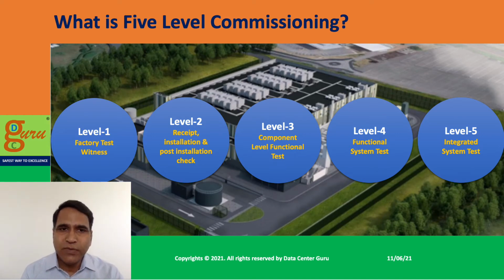Then level 2. Level 2 commissioning is all about whatever material is landing or being delivered on the site. Somebody has to check and ensure that all those systems, materials, and items delivered on the site are as per the design and specifications. Also, because normally when it gets delivered you cannot check the performance, but the specification and healthiness of the material delivered -- that there is no transit damage and so on -- needs to be checked. So obviously there is a script or checklist for each and every system and item, and people have to follow that to check that all those things are in line.